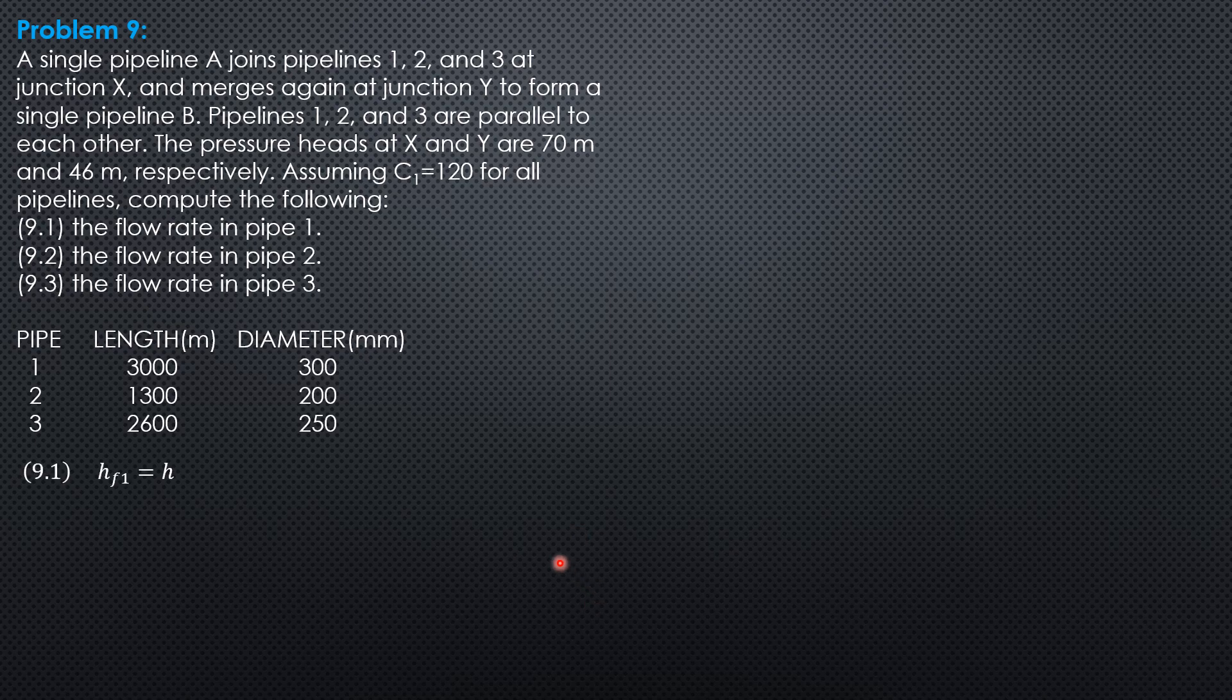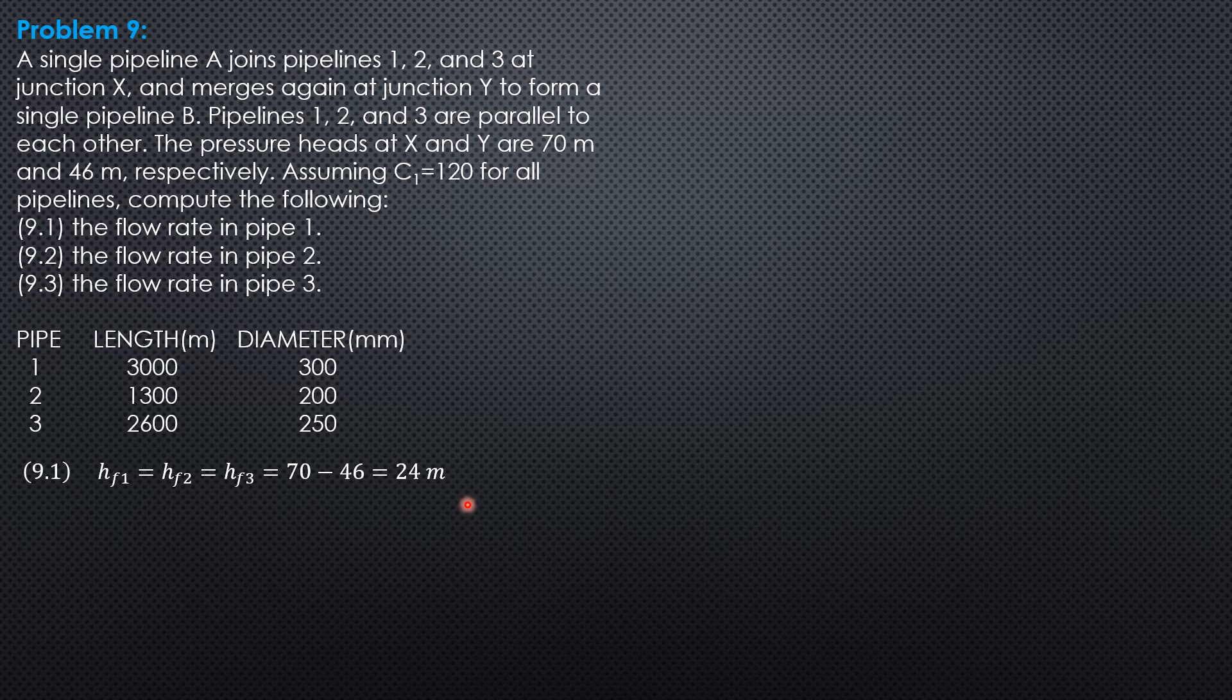So HF1 equals HF2 equals HF3 equals 70 minus 46 equals 24 meters. And the head loss and discharge formula for Hazen-Williams circular pipes is Q equals 0.2785 times C times diameter to the 2.63 times slope to the 0.54, where slope is head loss divided by length.